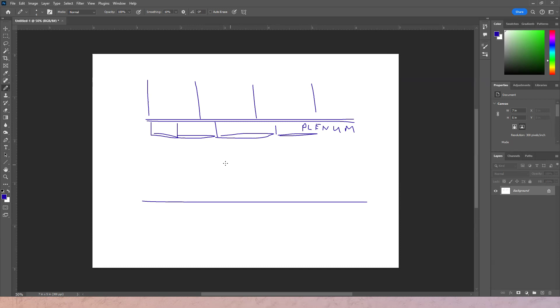So what's a cold air return plenum? Let me start with the other way - what's not a cold air return plenum? Let's say there are 3 rooms: room number 1, room number 2, room number 3. Notice that the plenum is shared by all 3 rooms. Of course there are doors and locks to all the rooms, but the ceiling space is open to all 3 rooms, for example.